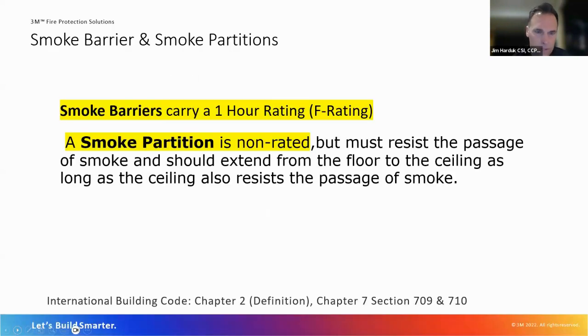Next, I want to talk about two terms that seem to trip up a lot of contractors and even a lot of architects. That is smoke barrier and smoke partition. Oftentimes, I hear these two terms used interchangeably. They are not. Anything that's labeled as a smoke barrier has to carry a 1 hour fire rating, which is an F rating. And I'll touch on that in a couple slides here. A smoke partition, however, is non-rated. So basically, a smoke partition is just constructed to resist the passage of smoke, and it should extend from the floor up to the ceiling, provided that the ceiling is also constructed to resist the passage of smoke. Next slide.